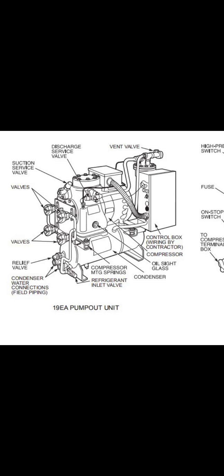The main procedure before starting pump down or pump out: you should circulate condenser water and chill water through the chiller. If you do not circulate the condenser water and chill water in the evaporator and condenser, what happens when removing refrigerant with pump down or pump out is that one vessel comes to low temperature and low pressure. The pump out unit sucks and removes the refrigerant. In this procedure, in the cooler or evaporator the temperature goes down, and if you have not run the chill water or condenser water, the water in the tubes freezes up and cracks or leaks the tube. This makes a big problem for your work.